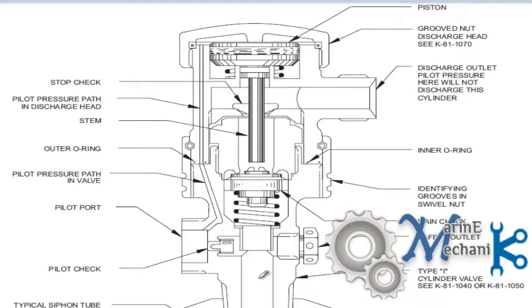Alright, so now, as you know, the bottle pressure, the CO2 comes here, along with the spring force, keeps this valve closed. Now you're operating the CO2 pilot bottle, the CO2 comes here. Now this pilot check valve cannot be opened by the lower pressure CO2 from the pilot bottle. The 1 or 2 kg CO2 from the small pilot bottle cannot open this pilot check valve. The reason is the CO2 inside the main bottle is at more pressure, so the back pressure is more, it cannot open. So it will travel through this path. I'll change the color. Just trace out this blue line.